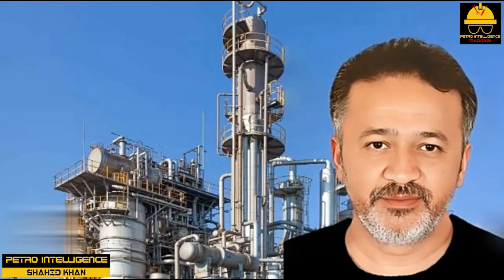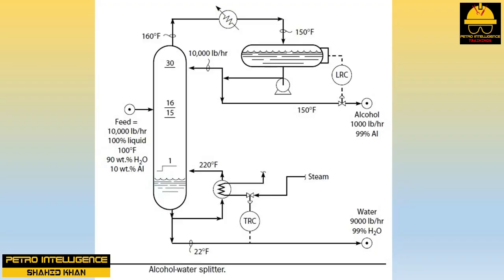Look at this picture. Alcohol is called the light component because it boils at a lower temperature than water. Water is called the heavy component because it boils at a higher temperature than alcohol. Raising the top reflux rate will lower the tower top temperature and reduce the amount of the heavier component, water, in the overhead alcohol product. But what happens to the weight of vapor flowing up through the trays — does the flow go up, go down, or remain the same?